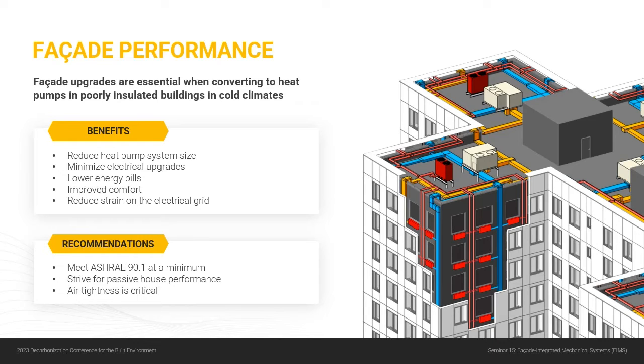But having this high performance facade does a lot of really important things for us. Brings down the heat pump size significantly. I mean, we're talking about buildings here that are mostly uninsulated that we're targeting. So you go from an uninsulated building to a highly insulated building. It's a huge reduction in the heat pump system size, which also means a big reduction in electrical upgrades to power those heat pumps. You end up with lower energy bills, so you can actually get some payback on your retrofit.